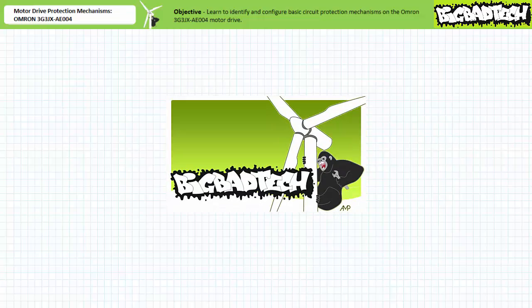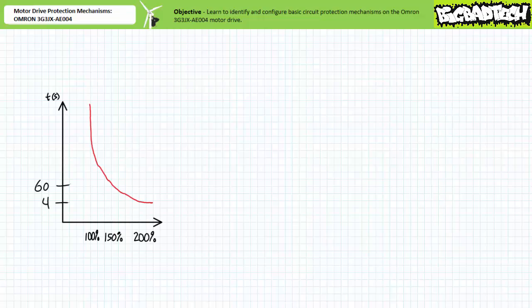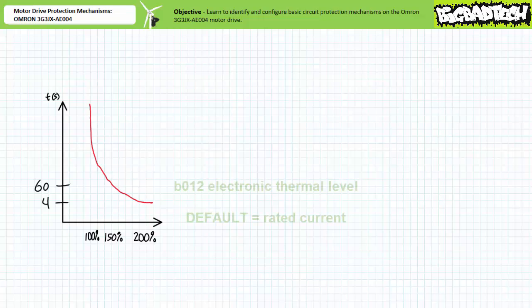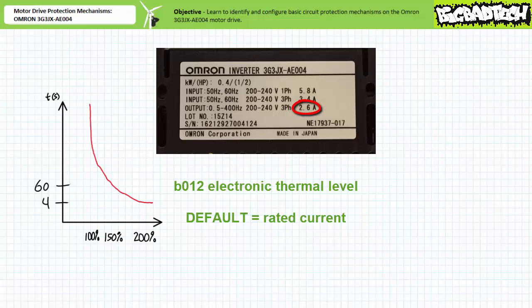A class 10 electromechanical overload relay will trip in 10 seconds if current is six times the rated value, with a curve describing the behavior of the overload at different current magnitudes. A motor drive can mimic the behavior of an electromechanical overload relay by continually monitoring both current magnitude and time. If a period of sustained high current draw is detected, an overload trip can be signaled. The OMRON 3G3JX AE004 motor drive coordinates overload response using protection parameter B012, electronic thermal level. The default level is the rated current of this drive — in this case 2.6 amps — as indicated by the nameplate affixed to the side of the drive.